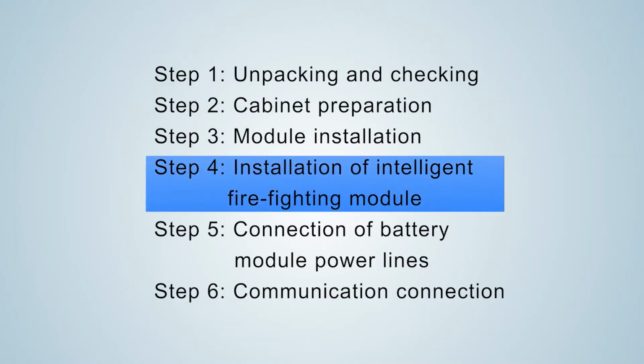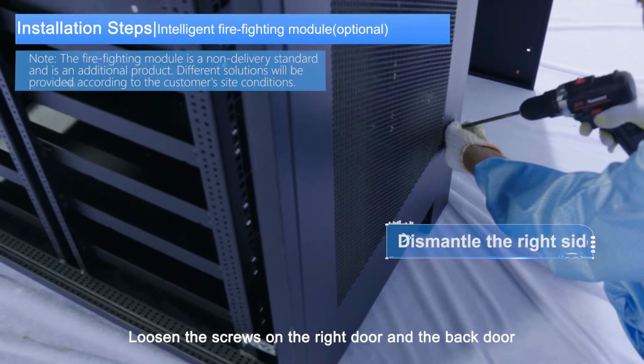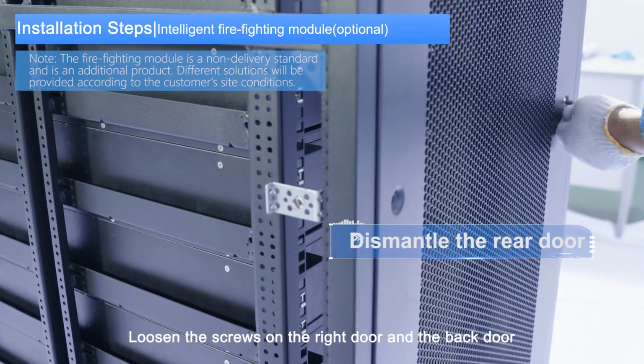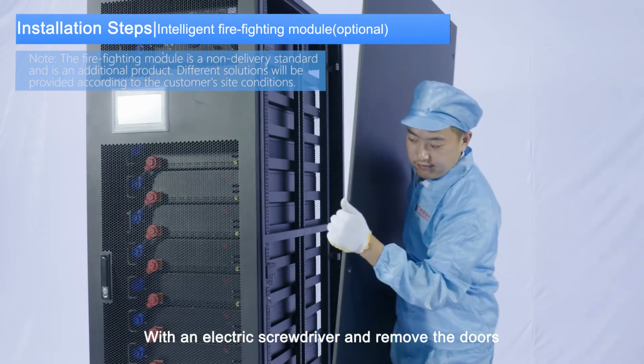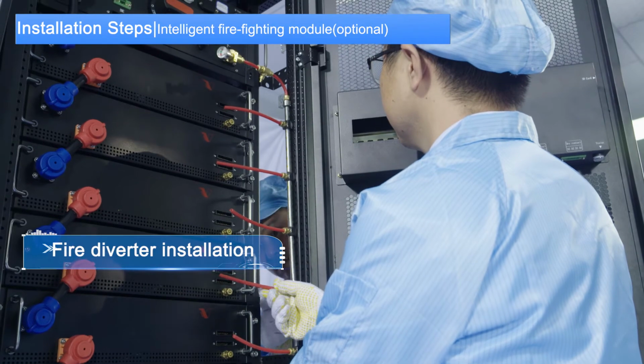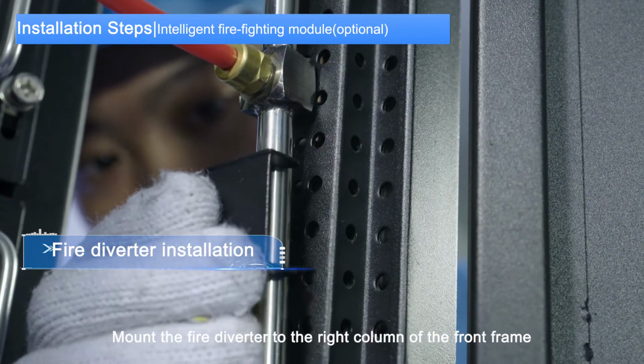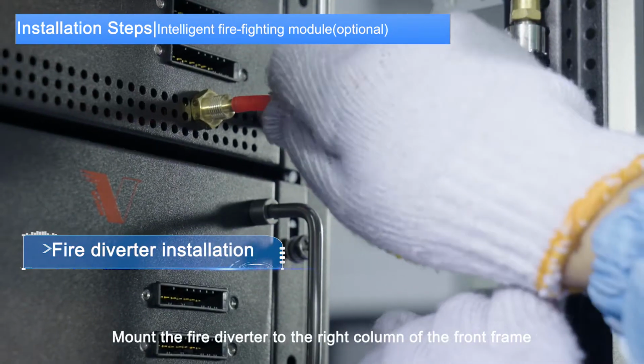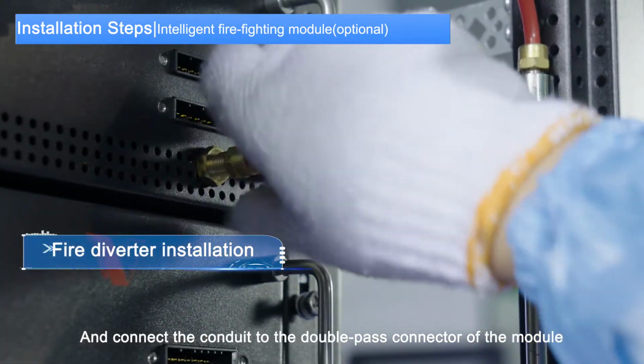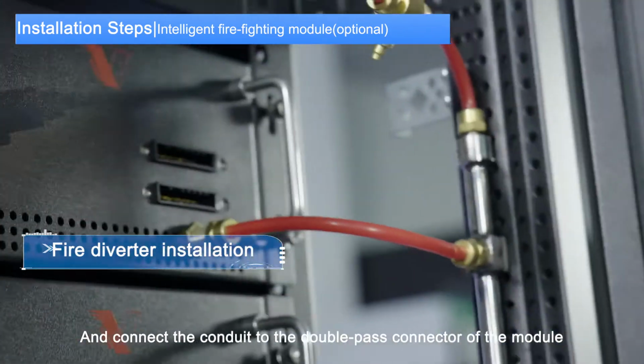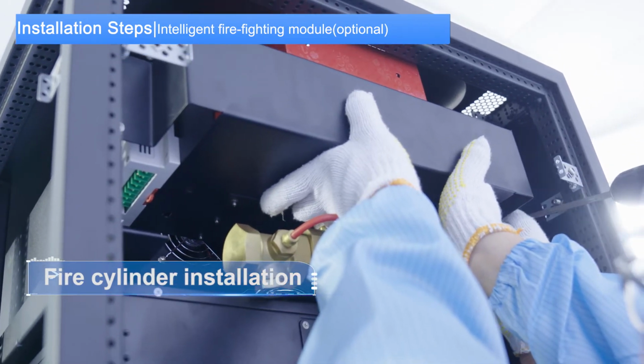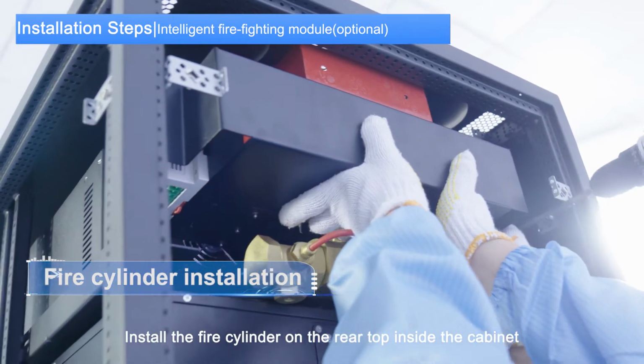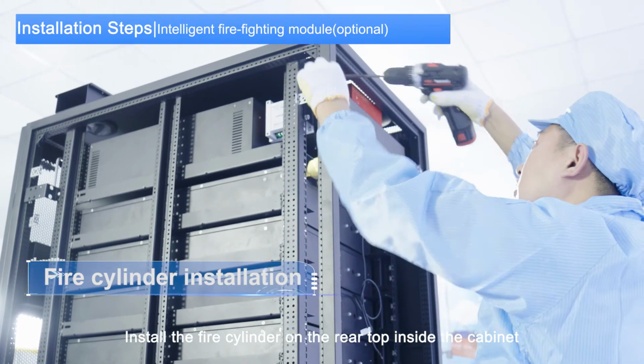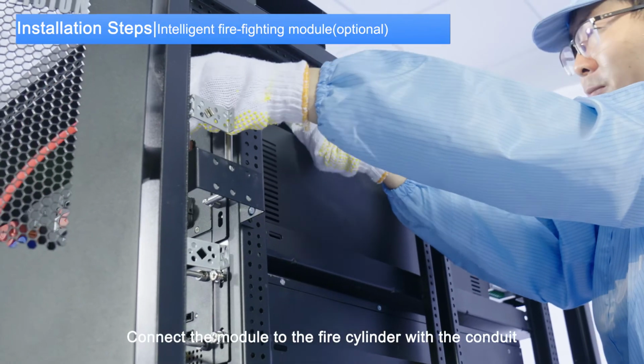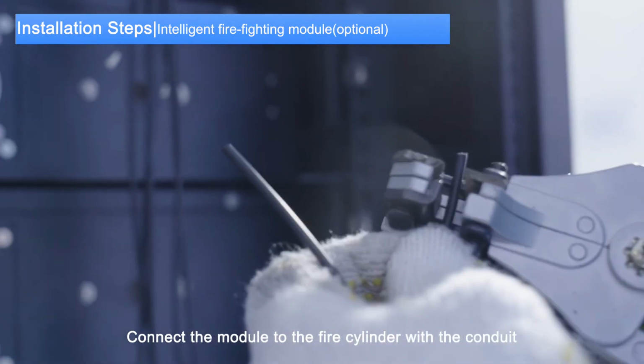Step 4. Installation of intelligent firefighting module. 1. Loosen the screws on the right door and the back door with an electric screwdriver and remove the doors. 2. Fire diverter installation. Mount the fire diverter to the right column of the front frame and connect the conduit to the double-pass connector of the module. 3. Fire cylinder installation. Install the fire cylinder on the rear top inside the cabinet. 4. Connect the module to the fire cylinder with the conduit.